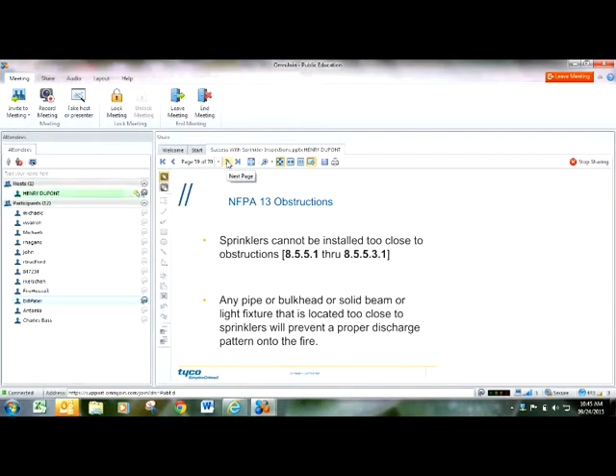Sprinkler obstructions, this is kind of a biggie. If you have sprinkler heads located right next to a soffit or a pillar and it's obstructing the sprinkler heads, they have to be spaced to spray around and under obstructions. So bulkheads, solid beams. If you've got a question whether a sprinkler head is installed too close to the beams, there's no magic rule that you just say, okay, well, it's 7 inches. It's got to be 7.